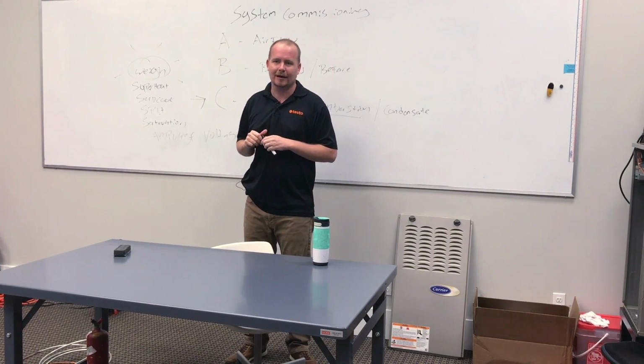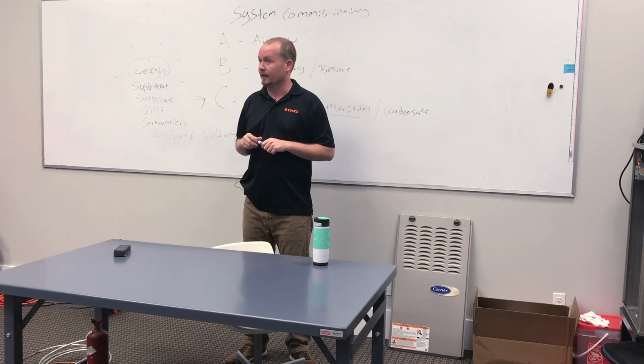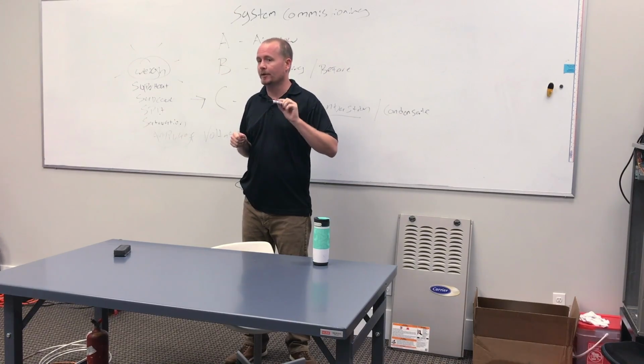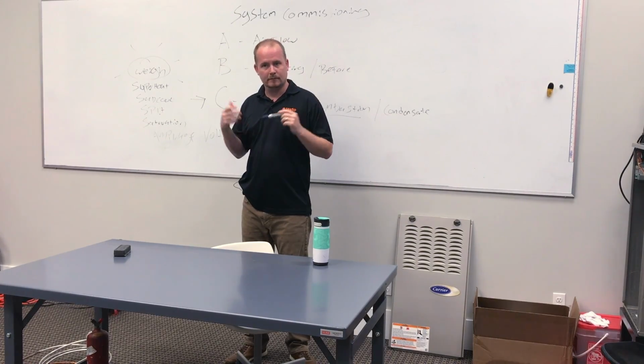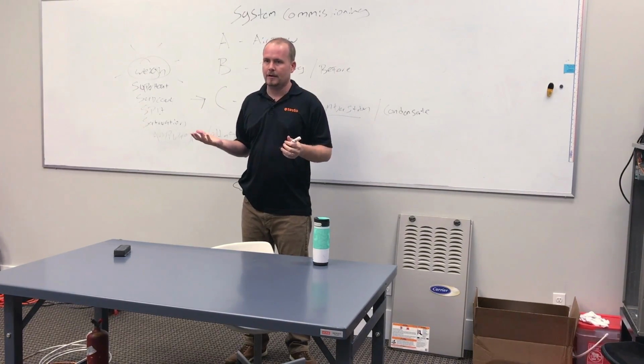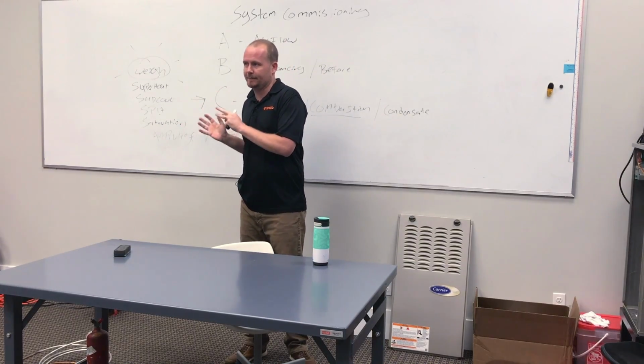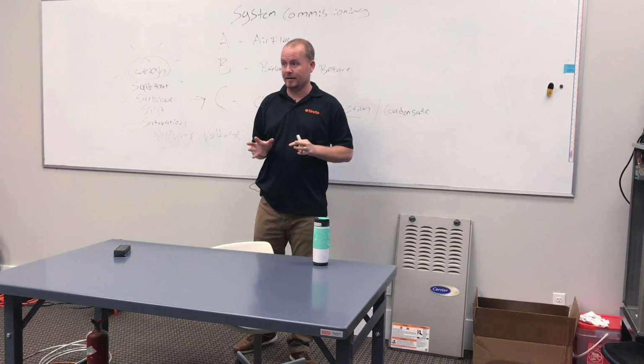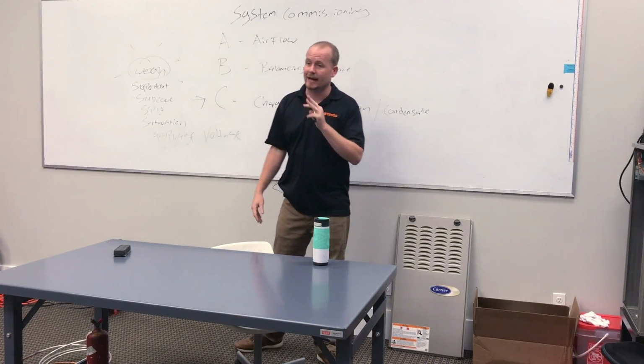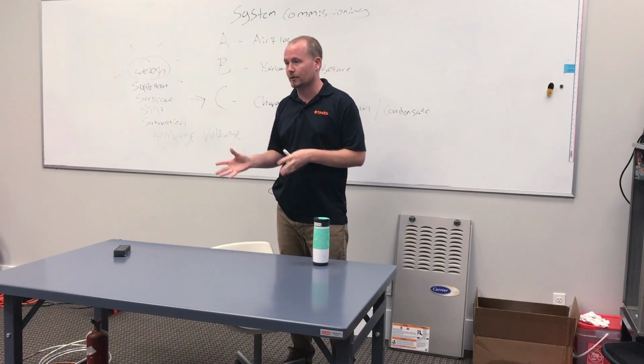And then the next question is, well, how do you do it? You do it with an airflow hood at every distribution point, at every return. How do you do it, right? Checking airflow is tough. So we use static pressure as our method, just knowing that in order for static pressure to work, a lot of other things have to be correct first, which is why static pressure is really tough as soon as that blower wheel gets dirty.